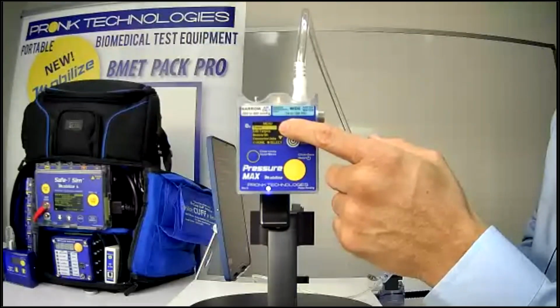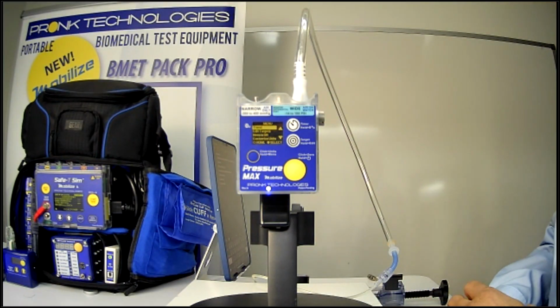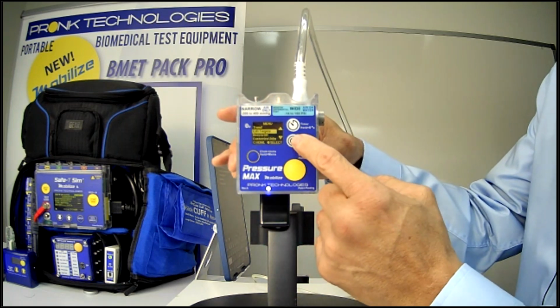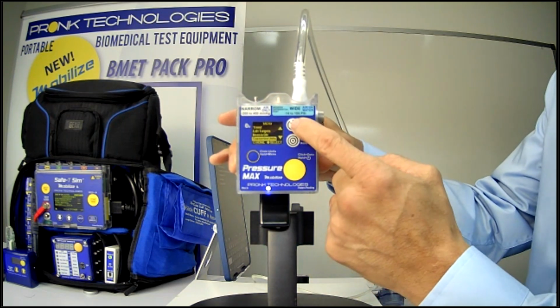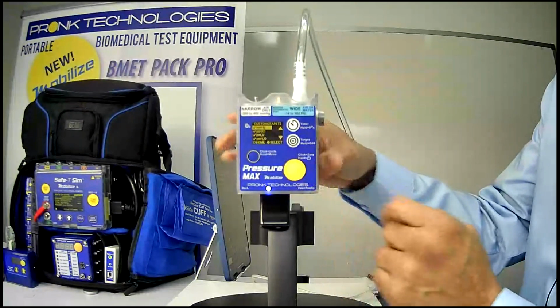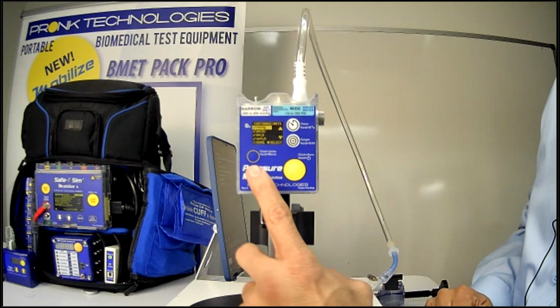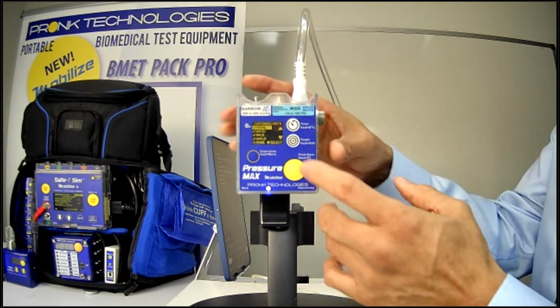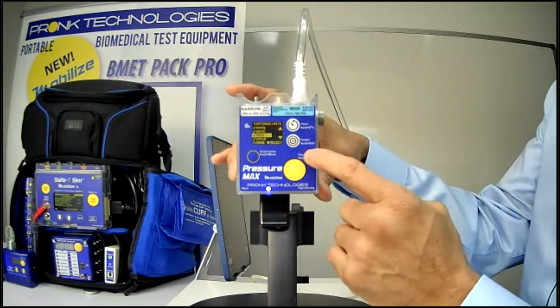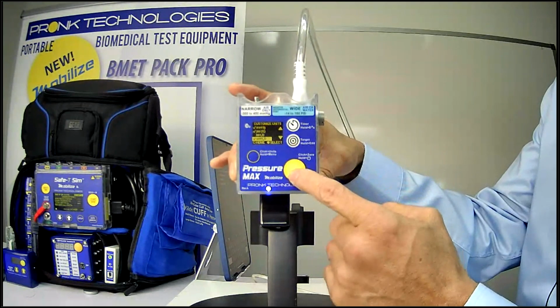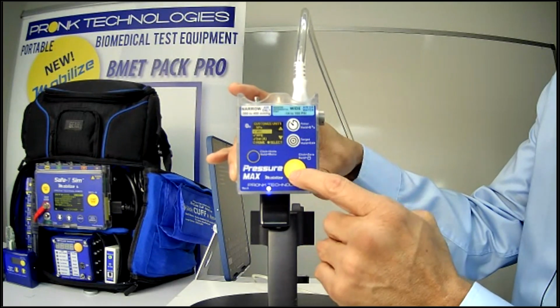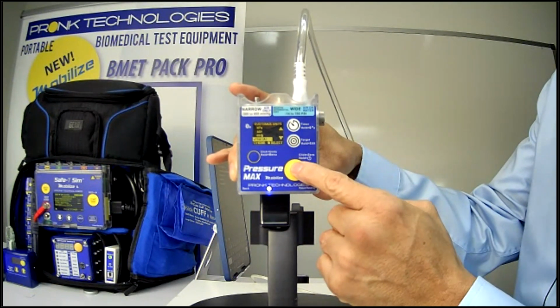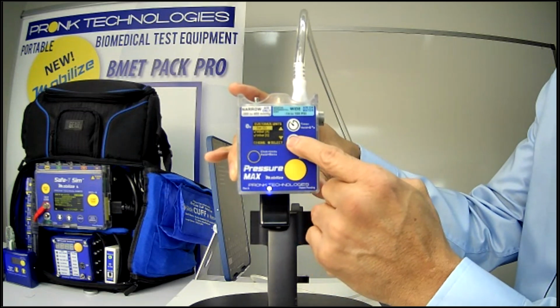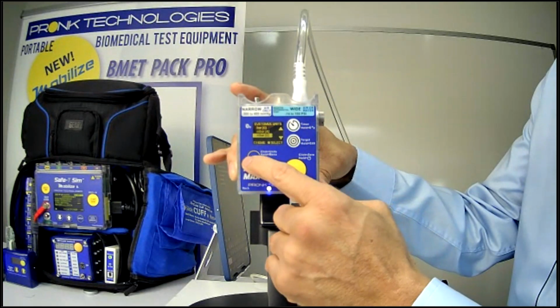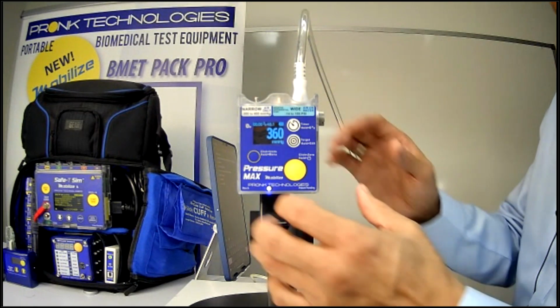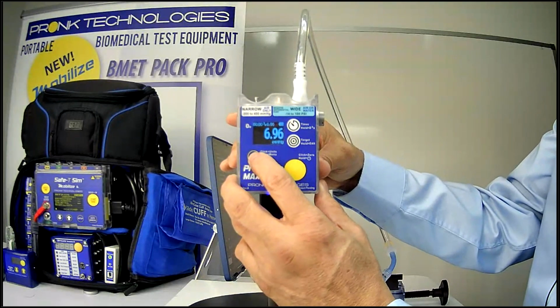You have the ability to trend pressures up to 15 minutes. It shows you pressure at 1-minute intervals. And you can also access the targets here, but you can also customize your units. So if I go to units, hit the enter key here, you'll see all the units of measure that you have selected will have a little checkbox here on the left. So if you know you don't want to utilize all those types of units of measure, maybe you only need to utilize 2, you can simply highlight them, uncheck them, so that you're basically deselecting them from the visible menu on the main screen. So I'm going to go ahead and just turn these off, and you can see all the units of measure that are available. We're going to just turn these off. I'm going to save it. And now I only will have the option to toggle between millimeters of mercury and PSI and nothing else.